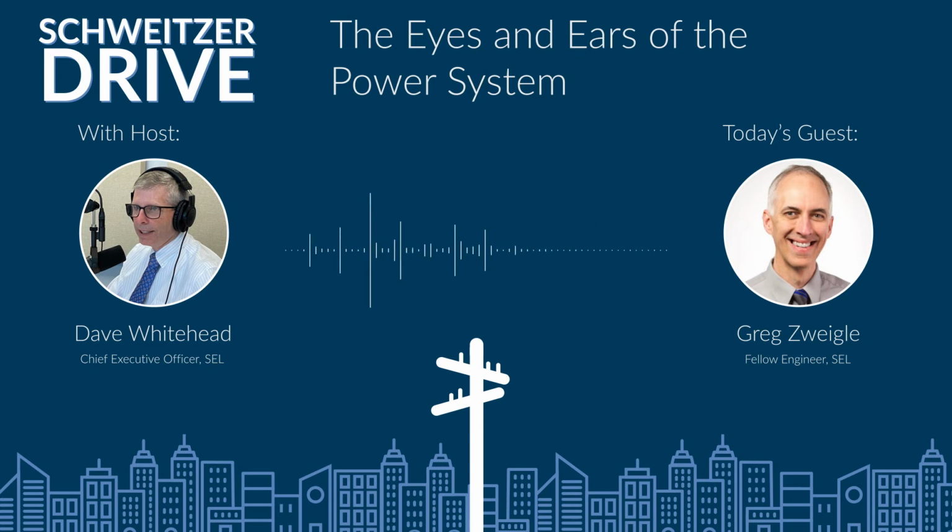Yeah, so for example, there's a great example in Central America, a problem that we solved for some customers. Central America is about 7 gigawatts, and it's connected to Mexico in the north, which is about a 50 gigawatt system. So keeping that connection between Central America and Mexico is really important to them because it improves the reliability of their system. In the past, they were experiencing these occasionally unstable oscillations. And with synchrophasors, a team of engineers at SEL built a system that could detect these oscillations and therefore help the system stay connected longer.